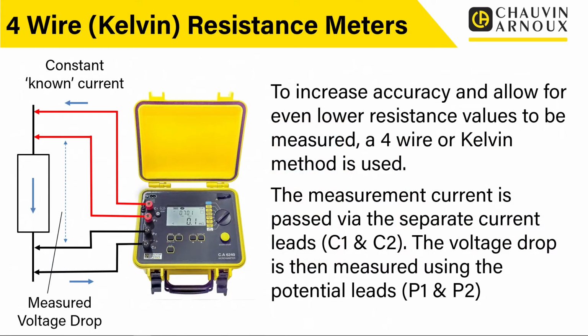Now, what's the next step? Well, if we want to increase the accuracy, generally in the industry, there are other methods, but we've pretty much standardized on this 4-wire, what we call Kelvin test method. And this is a really clever trick. When you understand it, you think, oh, actually, I really like the way that's been done. So rather than using 2 wires, we split our measurements up. We have 2 measurement circuits effectively, or two parts of the test circuit.